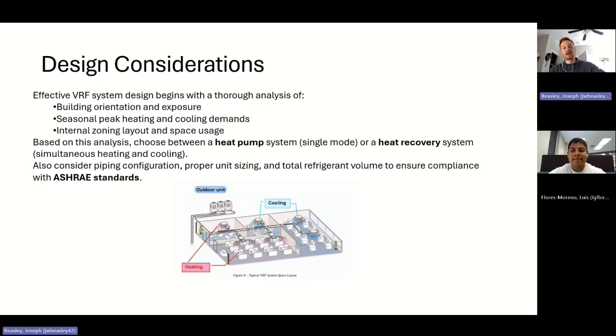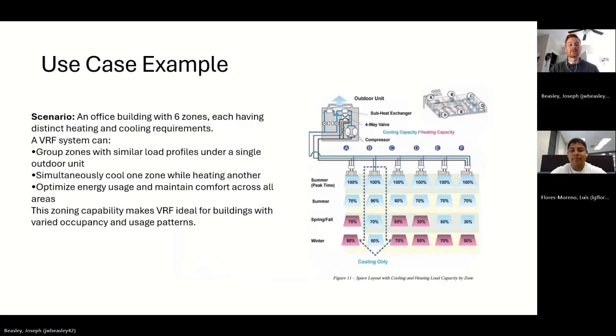And then based on your analysis of the building and how it's going to be laid out, you can choose from either a VRF heat pump system or a heat recovery system, which can do simultaneous heating and cooling at the same time, which can really save you some money. And also you need to consider the piping configuration, because VRF has a lot of pipes, and unit sizing, and just your total refrigerant volume, because you've got to stay within the ASHRAE standards.